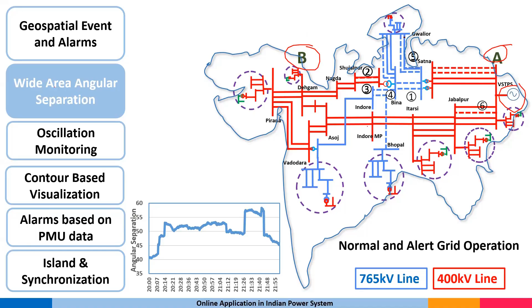Then you can see another tripping event. As soon as the line is closed, the angle reduces. Again, this major line trips, and you can see there is a very large change in angle. Then this line was closed immediately after tripping, and as soon as it was closed, the angle reduced. So this is the way angle separation is being utilized by the operator.